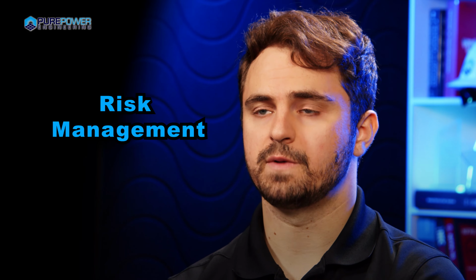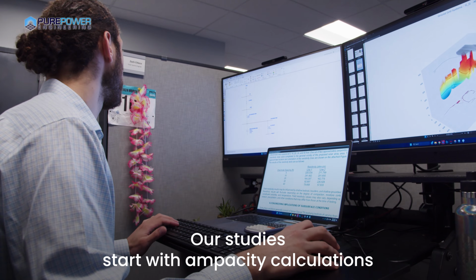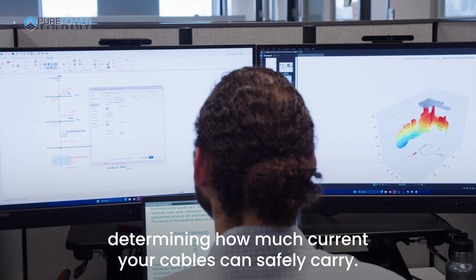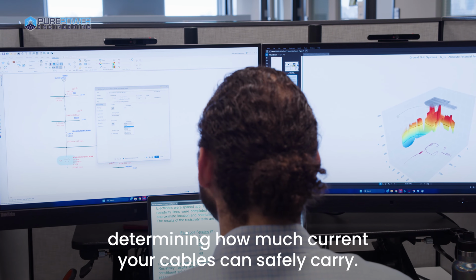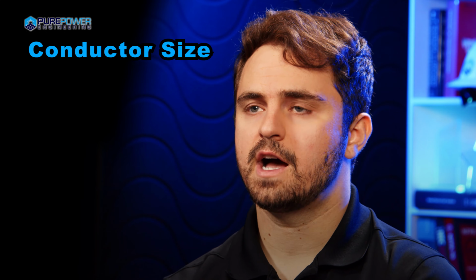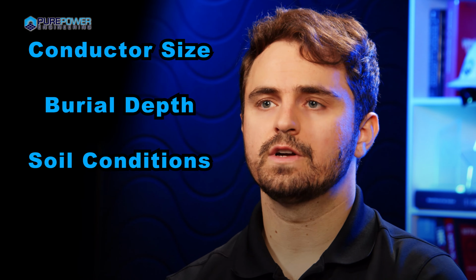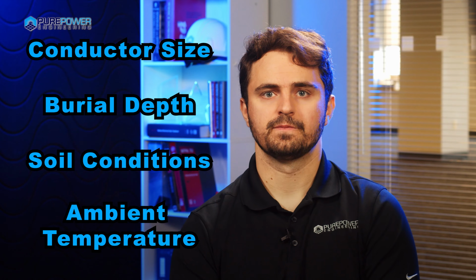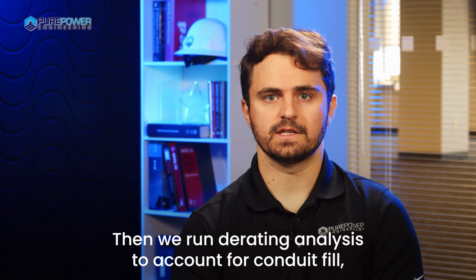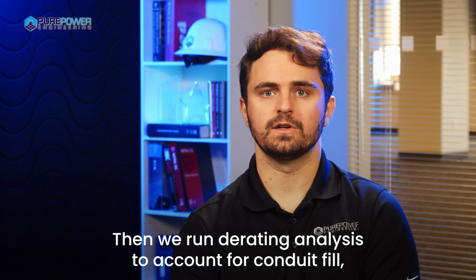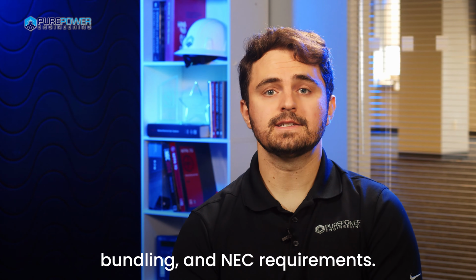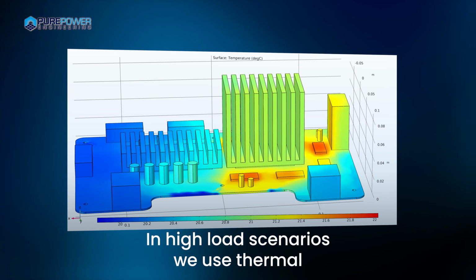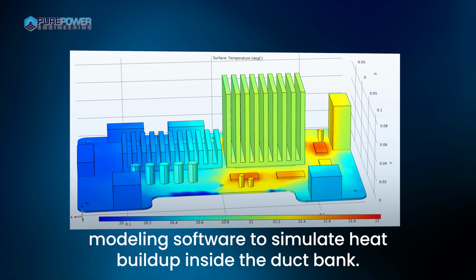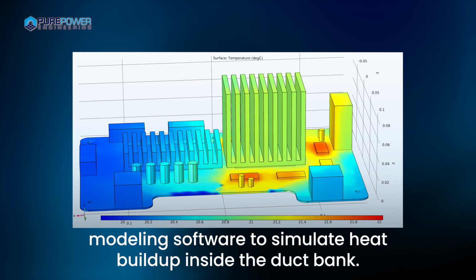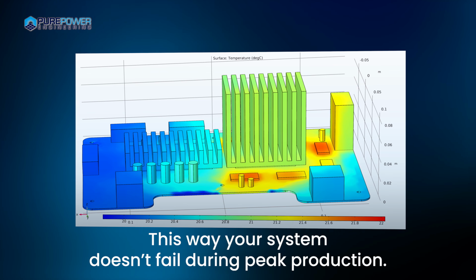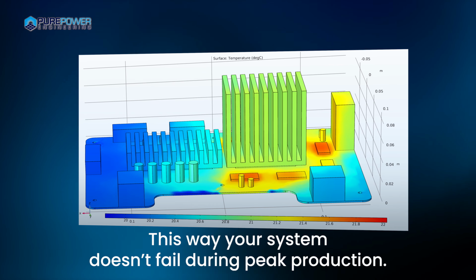It's risk management. Our studies start with ampacity calculations, determining how much current your cables can safely carry. This is based on conductor size, burial depth, soil conditions, and ambient temperature. Then we run derating analysis to account for conduit fill, bundling, and NEC requirements. In high-load scenarios, we use thermal modeling software to simulate heat buildup inside the duct bank. This way, your system doesn't fail during peak production.